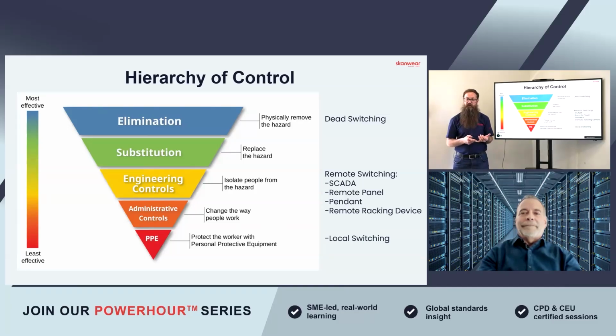So SCADA, can we operate the switchgear from a SCADA system, or could we use a remote panel outside of the substation where the switchgear is? Could we use a remote pendant, umbilical, or a chicken switch if you're in the US? Could we utilize a remote racking device? There's lots of technologies out there, either fixed or portable, that we may be able to utilize to take the person out of the equation.